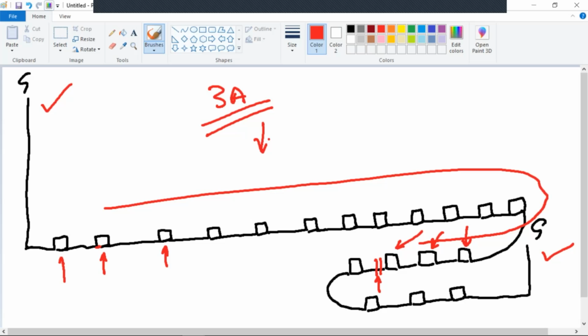Just be aware that if you drive into a subdivision and you've had a blown fuse here, the fault indicators may not work correctly if there was not enough load on the line. So you may have a red and a red and a red down here, and all of a sudden it turns white, white, white down on these. If there's not enough load on the line, you can't tell that because your power is out now, you might get a false reading between the red and the white indicator. That's one scenario. Now, if you drive into a subdivision that's built, it's been there for a while, you can pretty much rely on those indicators to be right.